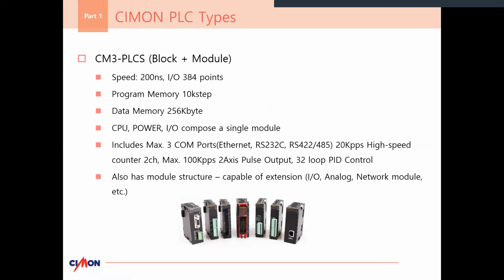When we step down to the PLC, the block, and the module type, you'll see our I/O count went down significantly, but the I/O max is actually still 1024. We do have an expansion module coming out relatively soon that will increase the I/O count. As a physical limitation, it's 384 right now because the PLCS can only expand up to 12 modules. In the near future, within a month or two, we'll be able to expand up to at least 16 bases, giving up to 1024 I/O count.